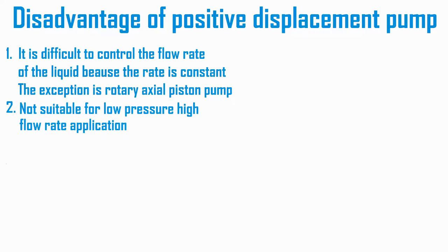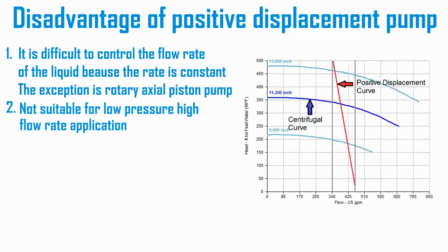Rotary positive displacement pumps are not suitable for low-viscosity liquids with low pressure and high flow rate applications, because the flow rate is almost constant regardless of discharge pressure. The centrifugal pump, on the other hand, will have a higher flow rate if the discharge pressure is lowered.